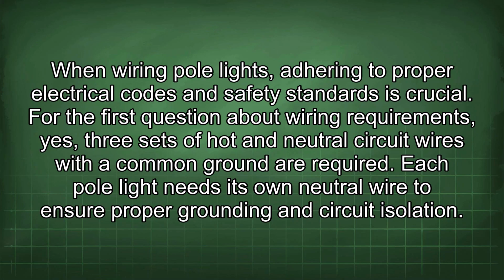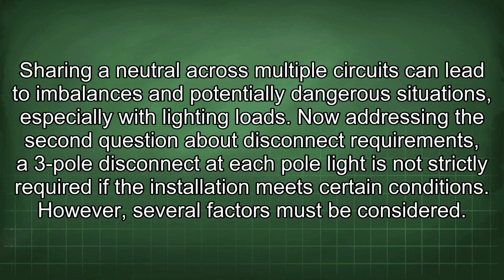When wiring pole lights, adhering to proper electrical codes and safety standards is crucial. For the first question about wiring requirements, yes, 3 sets of hot and neutral circuit wires with a common ground are required. Each pole light needs its own neutral wire to ensure proper grounding and circuit isolation. Sharing a neutral across multiple circuits can lead to imbalances and potentially dangerous situations, especially with lighting loads.